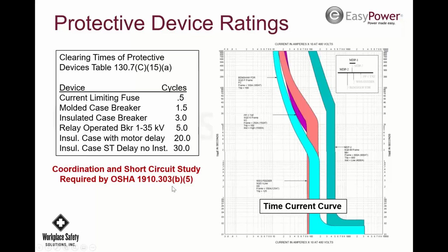So 1910.303(b)(4) and (b)(5) will tell you that you have to know the impedance of the system. You have to know the fault current, and you have to coordinate the system. So here's a bunch of time current curves. Let's just say this one goes to the main breaker feeding the facility. And that main breaker feeds the main distribution panel. And that main distribution panel has all the infrastructure on it. So all the breaker panels, all the motor control centers, all the bus ducts, all the chillers, everything is on there, transfer switches, whatever it is.